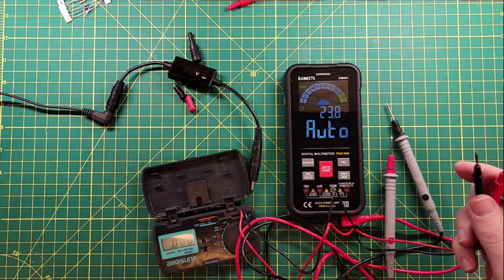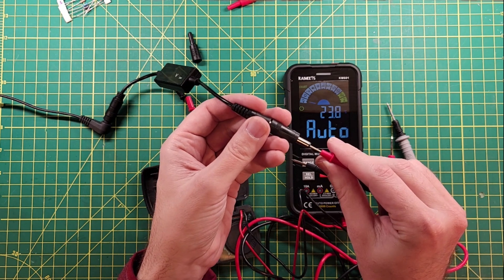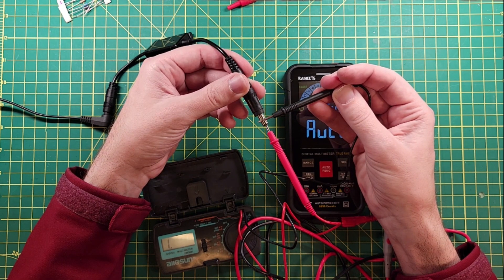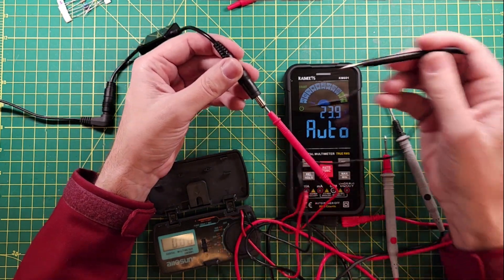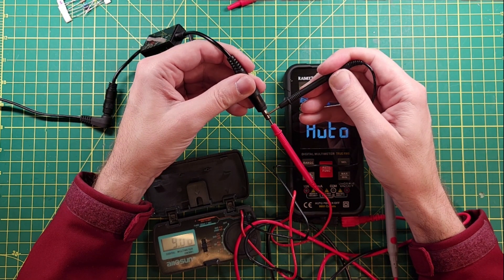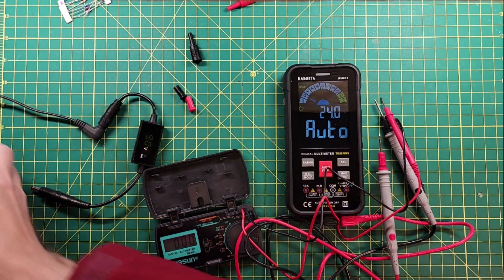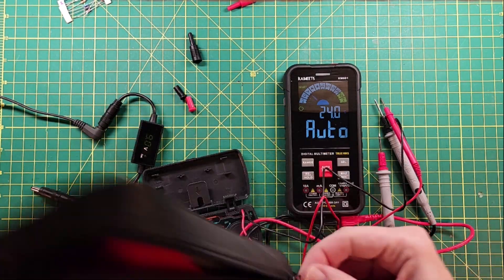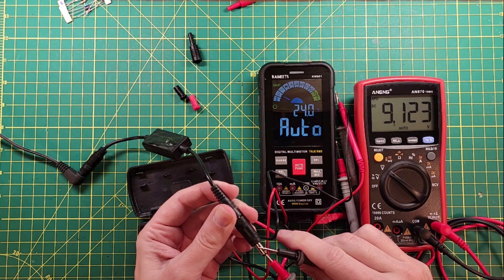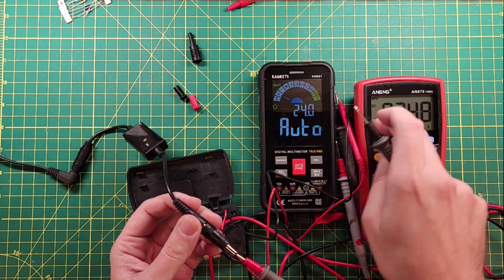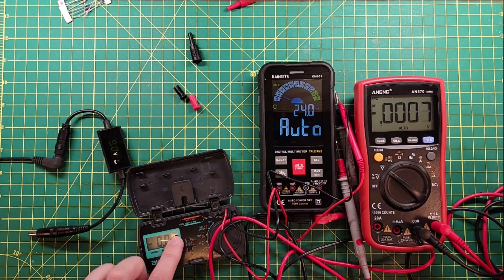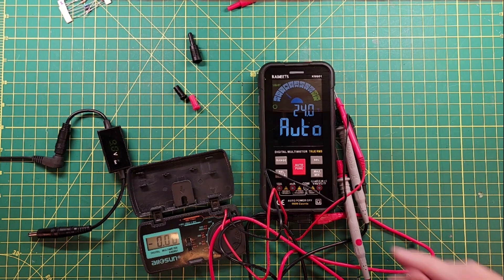And this one is not an auto meter. So we'll put the probe in. Wrong range. 9.06. And then let's compare it to this one here. 9.12. OK, so these two here produce the same result. This one's close enough. I'll consider that a pass.